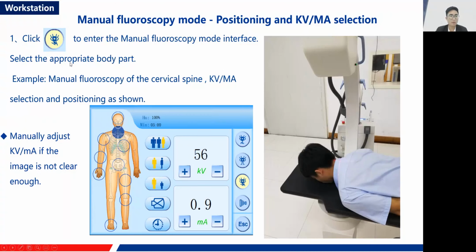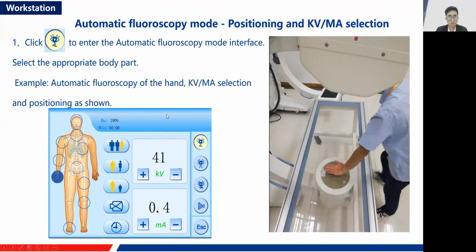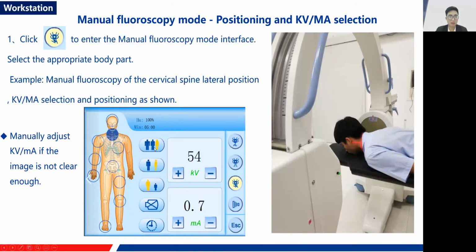Okay. And the manual fluoroscopy mode is also similar to the automatic fluoroscopy mode, and you select the body part and body size, which are also very similar. There you need to adjust the kilovolt and the milliampere manually. So it is a manual mode. You need to adjust them according to your experience and your radiography knowledge. Of course, if you find the image is not very clear, you need to adjust them again until the image is clear enough, right?